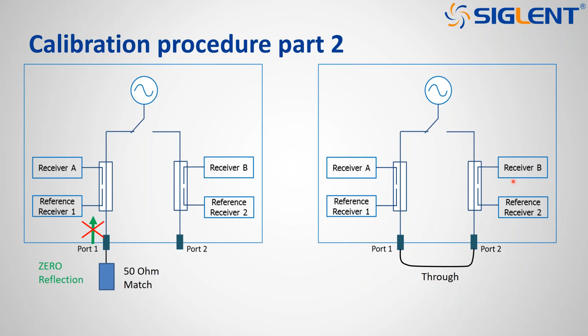Are we now completely safe? Not 100%. There are some exceptions, especially if you have a device which has a very high insertion loss, and if this insertion loss is higher than the typical crosstalk of the VNA. Typically this is 100 to 120 dB, which is defined as crosstalk, and this just happens on high isolation devices. It means if there is a switch in between, which is open at a certain state, then of course nothing comes back, and then you have issues, and you have to do an isolation calibration, because the normal calibration does not cover this high isolation part.